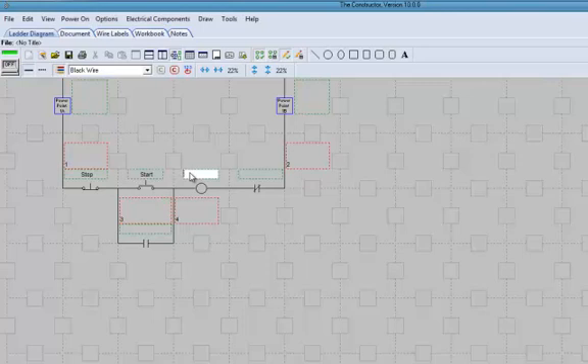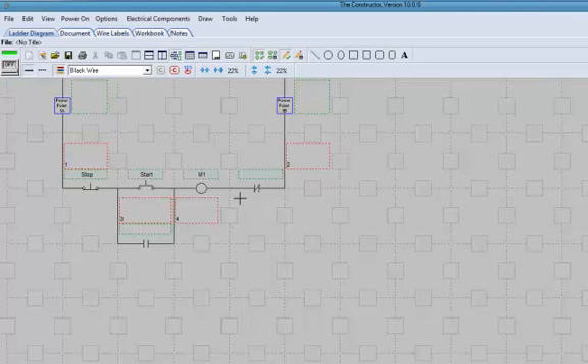Now I just want to stop here and provide a word of caution. You need to make sure that this coil is labeled first before you try to do any of these contacts, and you'll see why in a minute. So this is my motor starter, motor starter one coil. Now, I could also label this M1 because it is M1. However, this software is going to not open and close that contact when I go to try to simulate it.